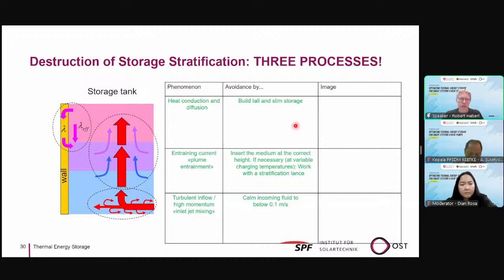To avoid that, you can build tall and slim storage tanks. The second is the entraining current or the plume entrainment, meaning you bring in the heat in a part of the storage tank where it's not the same temperature as in the surroundings. Then the water has to find its way on its own to the correct position, and on that way it will transport some more water to the wrong position and lead to mixing. Therefore, you should insert the medium at the correct height. If necessary, you can work with a stratification lance, as we saw before. For solar heat, you put it usually in the lower part of the storage tank. And to avoid this plume entrainment mixing, you can use a stratification lance.